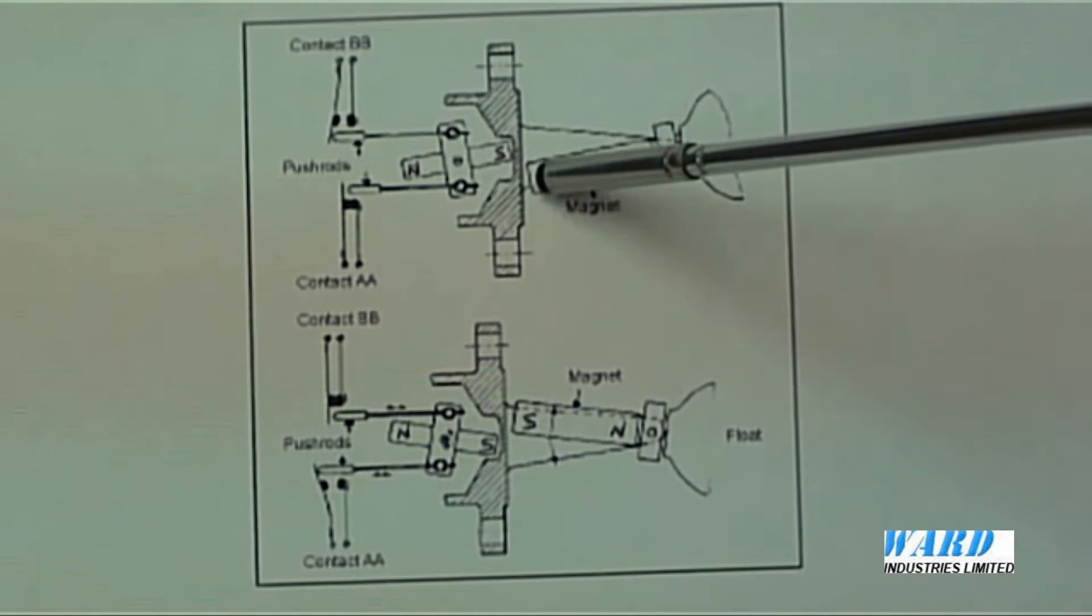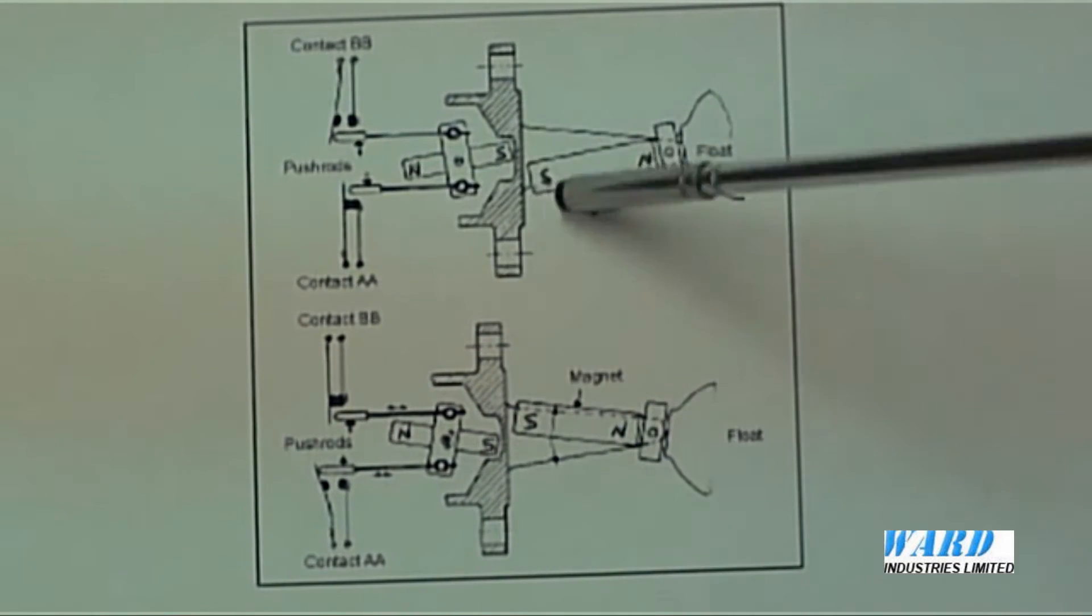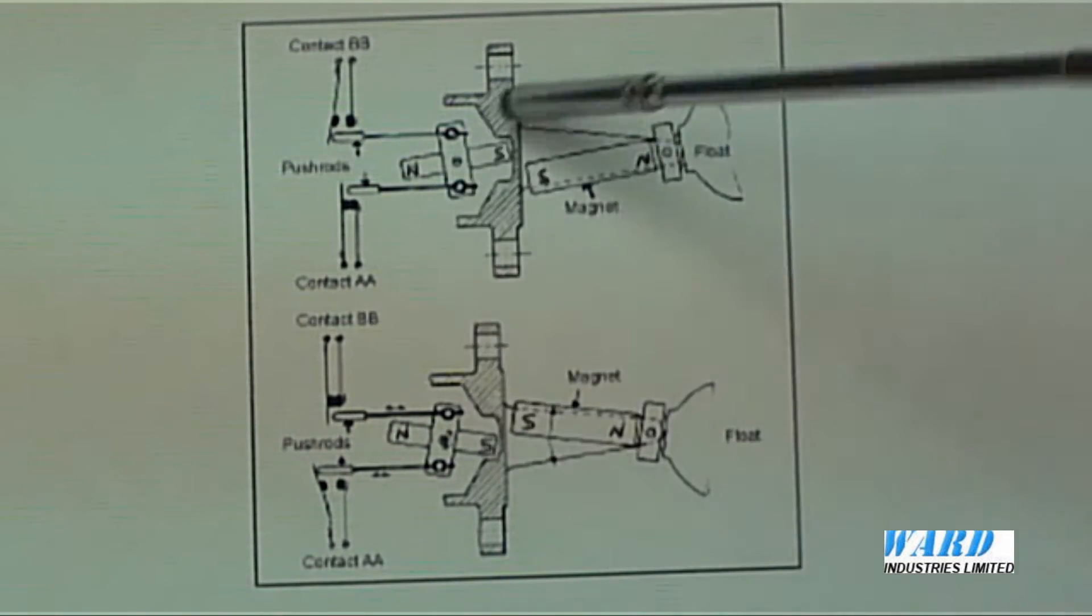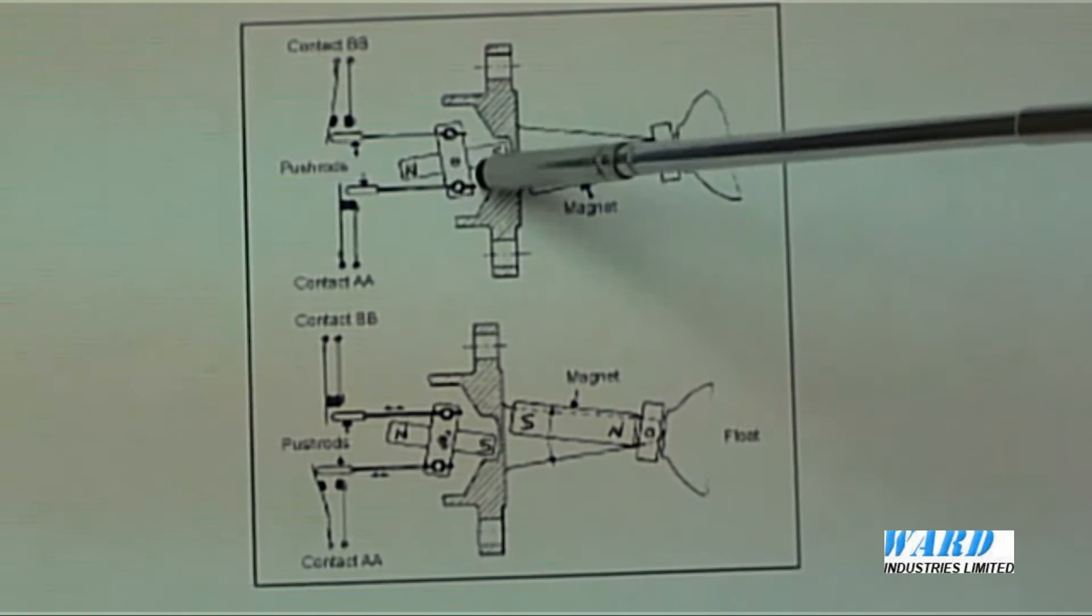So, we will have south pole facing a south pole, and consequently, the south pole in the switch head mechanism will be repelled and snap over. This causes the snap action operation in the switch mechanism.